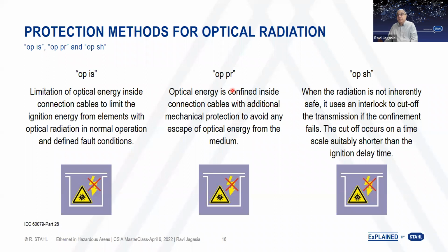OPPR is fiber optics protected. Basically, you are protecting the fiber optic cable or the connection cable in an additional conduit in a pipe, which would then ensure that if there are breakages, the pipe is acting as a protection from the radiation being exposed to the hazardous area. Going forward, it is OPSH, that is interlock.